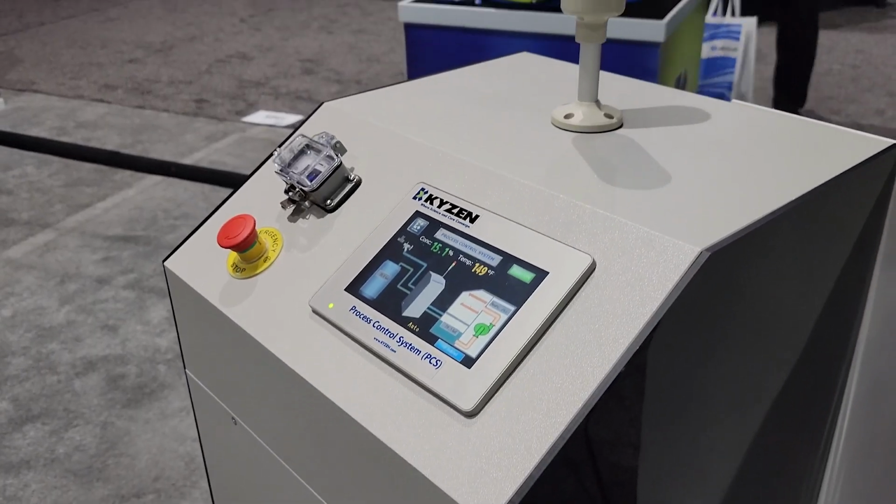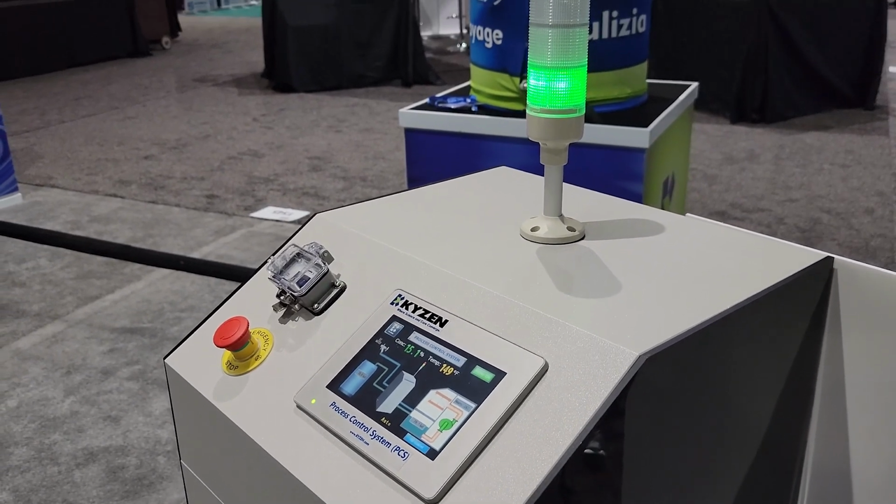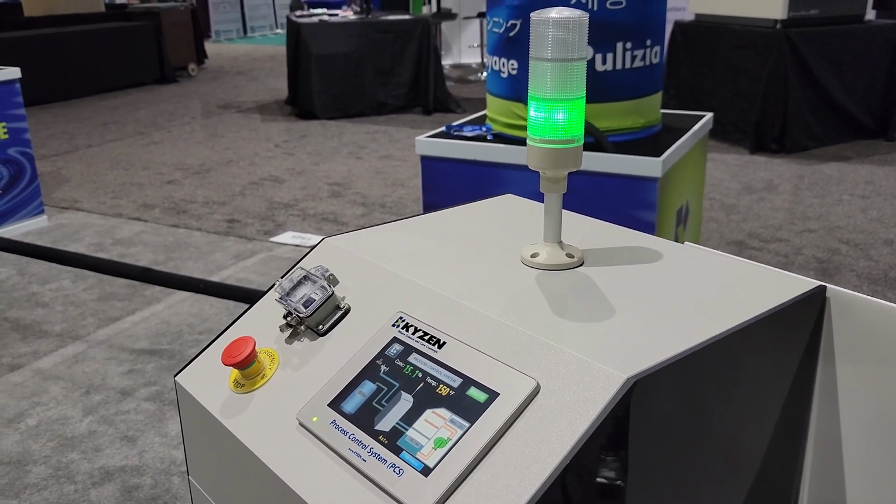control the wash tank in an inline, because an inline wash process is very dynamic. An inline has holes on both ends, which means it has exhaust because we don't want any smells to come out. But now I've got an exhaust and I've got air knives coming in between the sections, so I've got giant flows of air coming in, giant flows of air going out, which is a very dynamic situation compared to your sink at home where you put a little suds in there and you just sort of rinse it off a little bit.